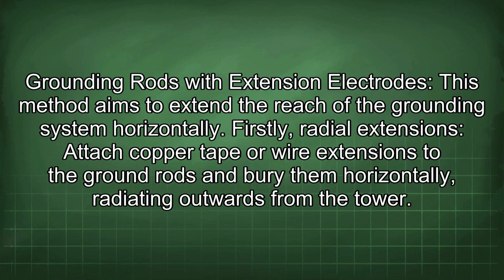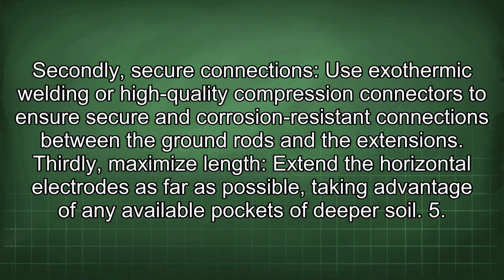4. Grounding rods with extension electrodes. This method aims to extend the reach of the grounding system horizontally. Firstly, radial extensions. Attach copper tape or wire extensions to the ground rods and bury them horizontally, radiating outwards from the tower. Secondly, secure connections. Use exothermic welding or high-quality compression connectors to ensure secure and corrosion-resistant connections between the ground rods and the extensions. Thirdly, maximize length. Extend the horizontal electrodes as far as possible, taking advantage of any available pockets of deeper soil.